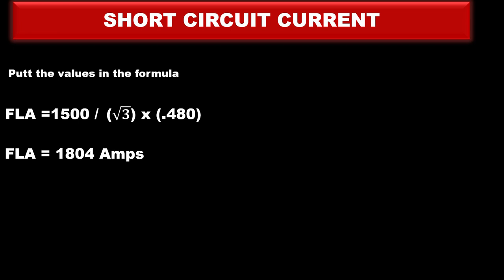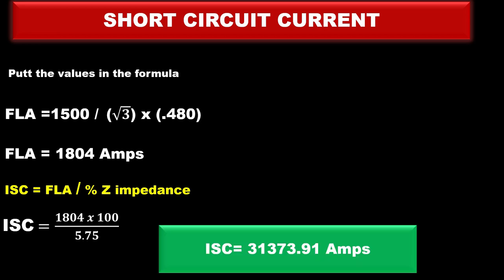Now we know that full load ampere is 1804 amperes. Put this value in the short circuit current formula. The short circuit current formula is full load divided by percent of Z impedance. 1804 multiplied by 100 divided by Z impedance 5.75, the answer is 31373.91 amperes.